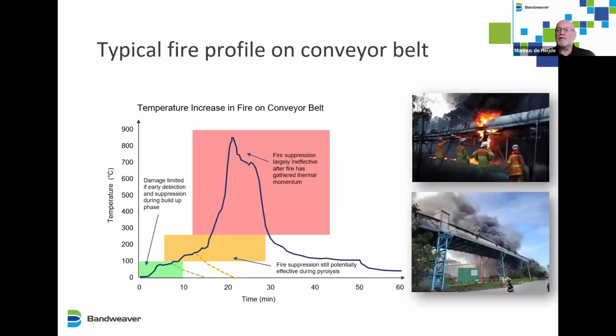So this fire profile, you can put into any fire, but this is typical for a fire profile for a conveyor belt. So the very early stages, early detection, preferably before there's a fire, you can still do something with the maintenance team. But when there is an early detection, the suppression system will probably be able to suppress the fire. Once the fire develops further, fire suppression might still work, but there is a big chance that it will develop into a thermal runaway, what we call it, in which case it is just watch and look everything go up in fire, and at that time it is far too late. So what we want really is to detect in or even before the green zone.